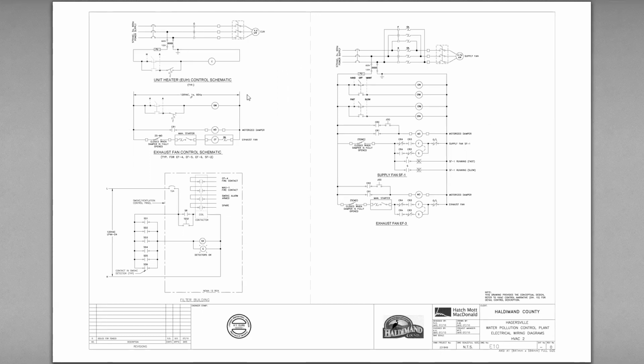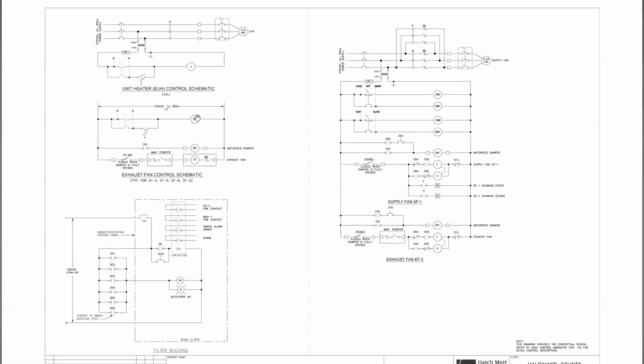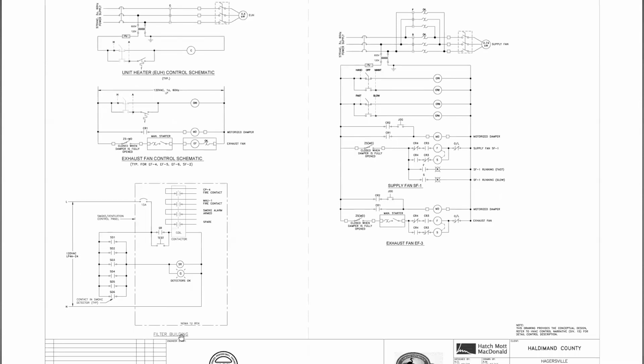More circuits. So again, I know a couple of weeks ago, I kept saying you'll see lots of motor starter circuits. I think you might already be getting the picture that 90% of drawing review is motor starter circuits, at least for my industry. But even if it's not a motor starter circuit, it's contacts, it's relays, overloads. Here's some more supply fan, EUH, which is a unit heater.